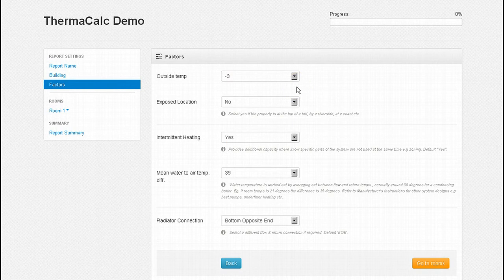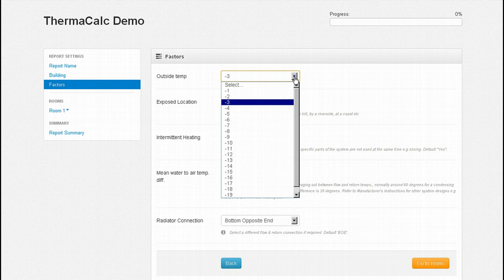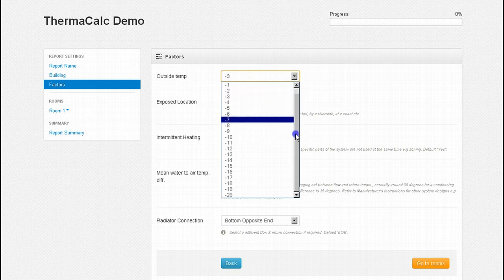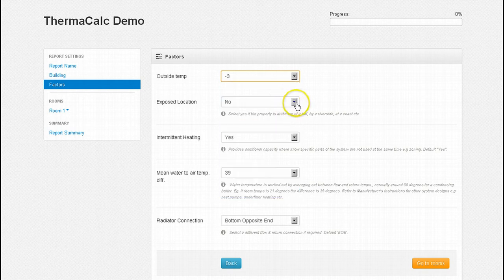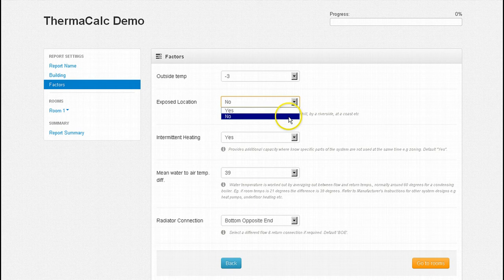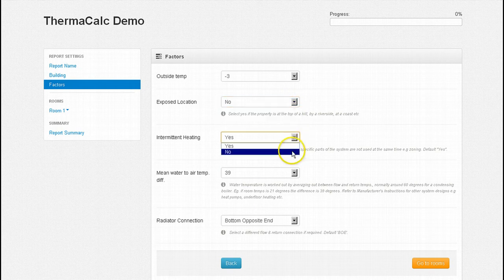The design of any system relies on the input of several key factors, one being outside temperature. This will be your estimate based on geographical location. The default is minus 3 degrees C with options to go down as far as minus 20. Select yes in the exposed location field if the property is on a hill, riverside or by a coast for example. And select yes to intermittent heating if known parts of the central heating system are not to be used at the same time, for example zoning.